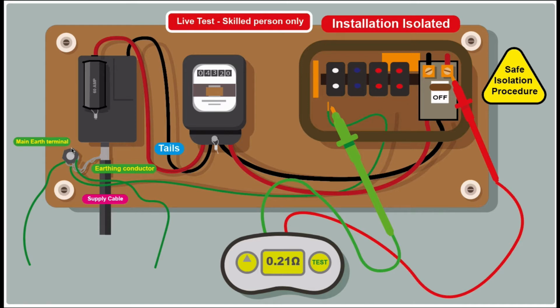And as I mentioned in the previous section, we're going to get parallel paths here, because we measure here between the line and the earth. If you follow this path round, it goes to the earthing terminal here. We've got these other conductors coming off it, which possibly go to our bonding, our gas and water. Sometimes you see connections and no services, you're not quite sure what they're actually for, if they're actually connected to anything. Doesn't matter, it's all getting ripped out.